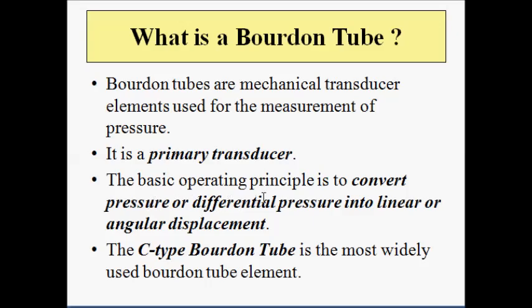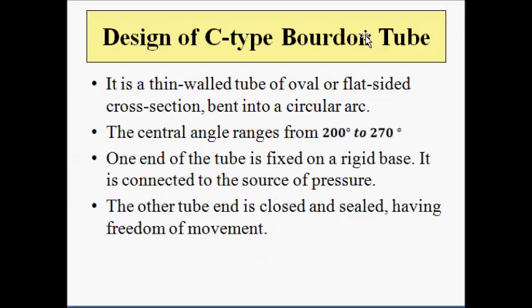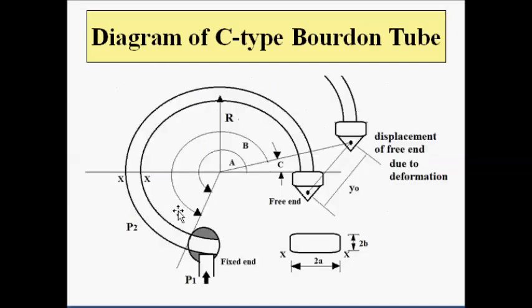The basic operating principle is to convert pressure or differential pressure into linear or angular displacement. Normally the C-type Bourdon tube element is used commonly, which we are going to discuss today. The C-type Bourdon tube is a thin-wall tube of oval or flat-sided cross section which is bent into a circular arc. The central angle ranges from 200 degrees to 270 degrees, forming a C-shaped structure.